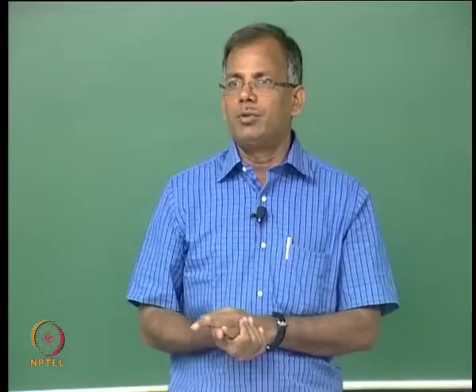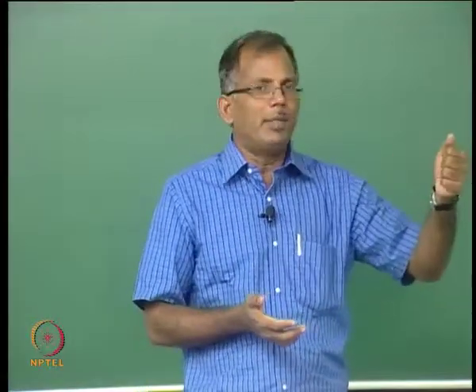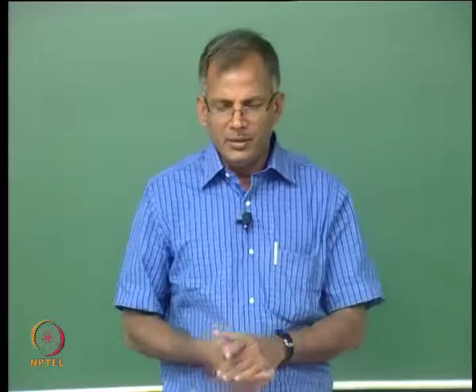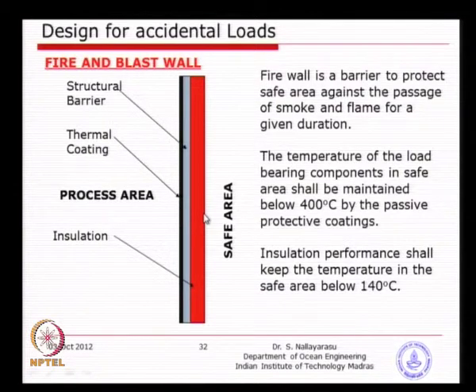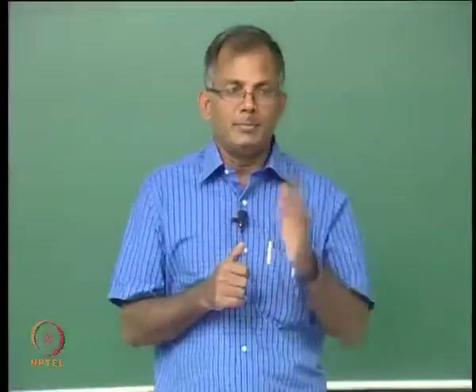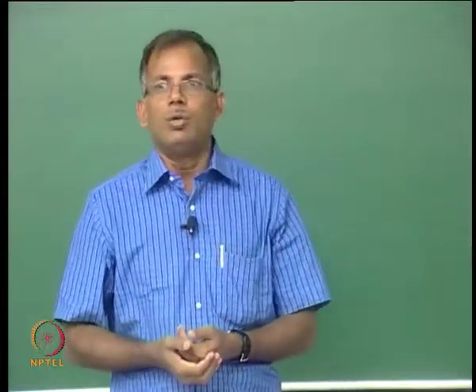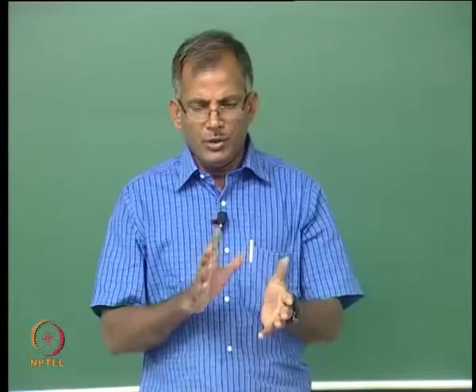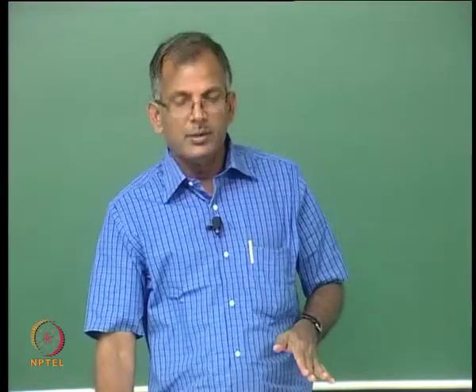You design the thickness of glass wool based on the incoming temperature and the required temperature on the other side. Additionally, you can create an air gap between the steel and the glass wool — air gap is also a good insulator of both sound and temperature. Normally a 100 mm gap is given between the steel and the insulator, which stops propagation of sound as well as temperature. You have to come up with a cross section that reduces temperature and meets the required design.